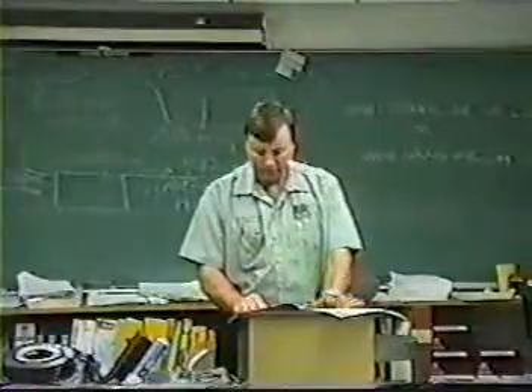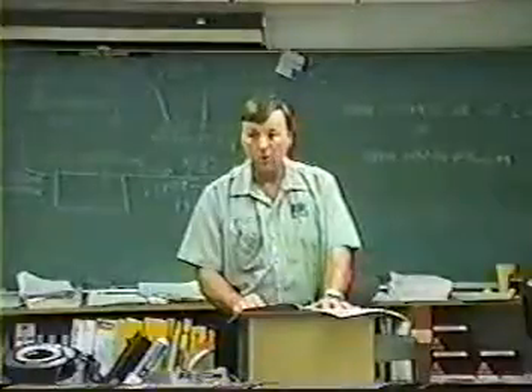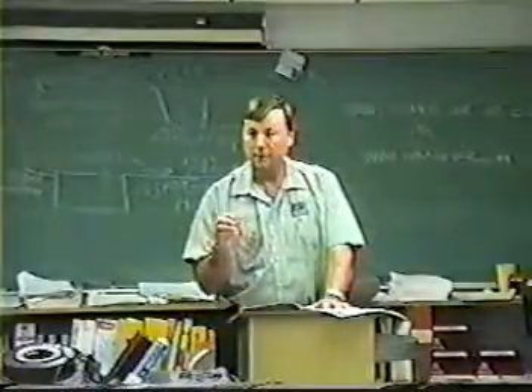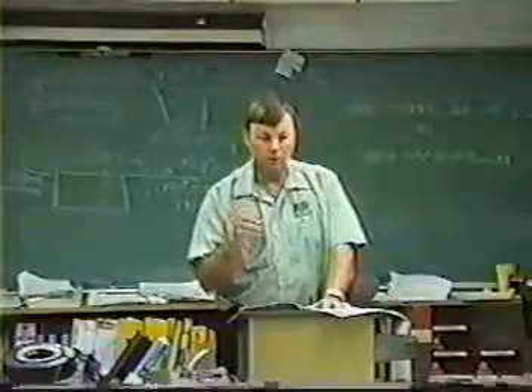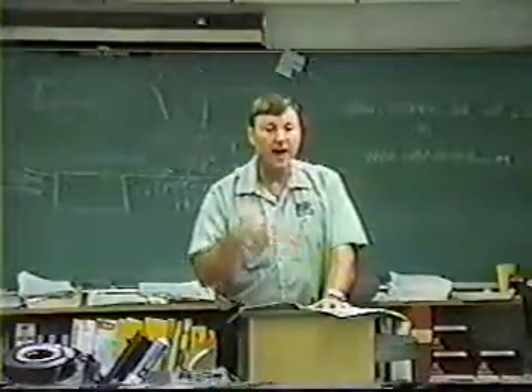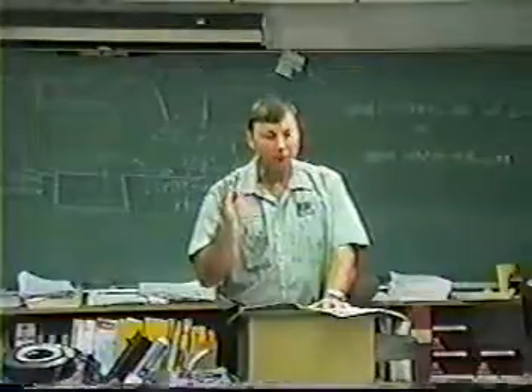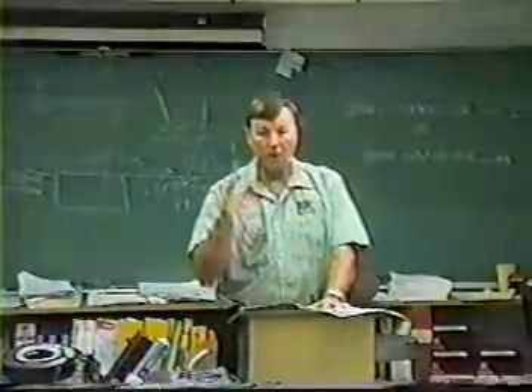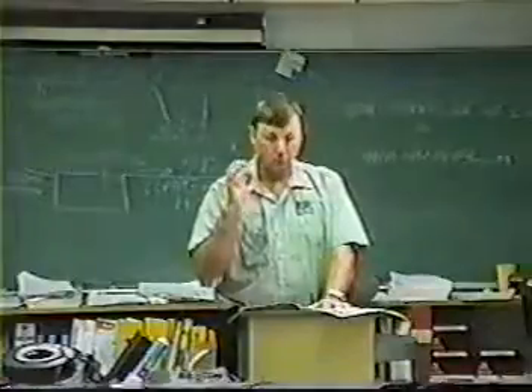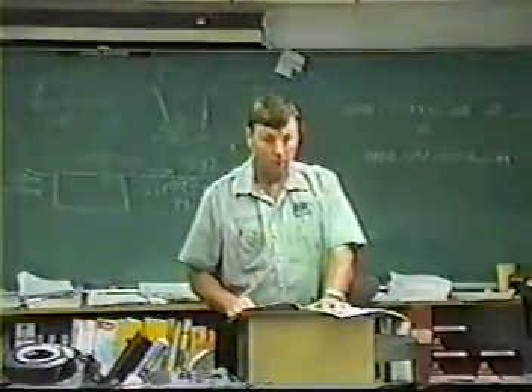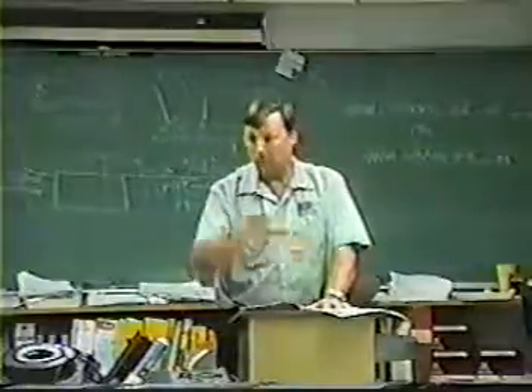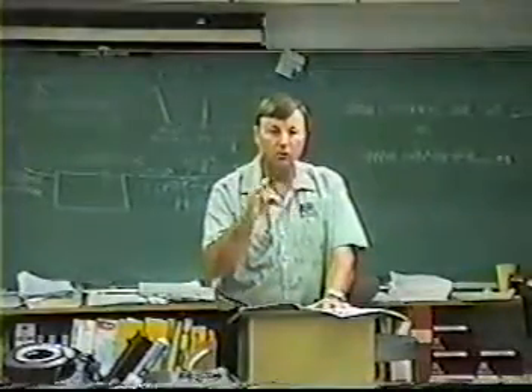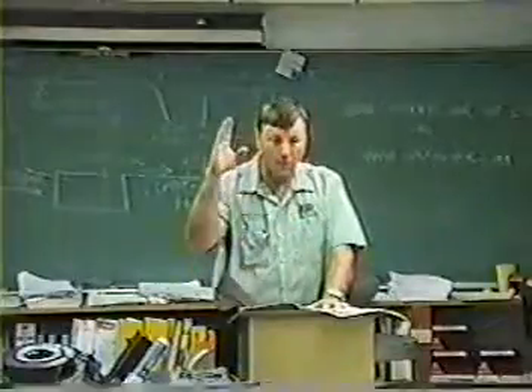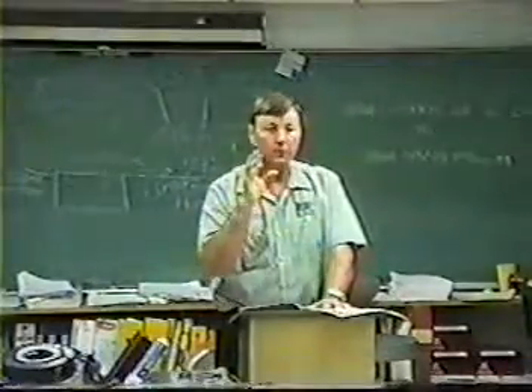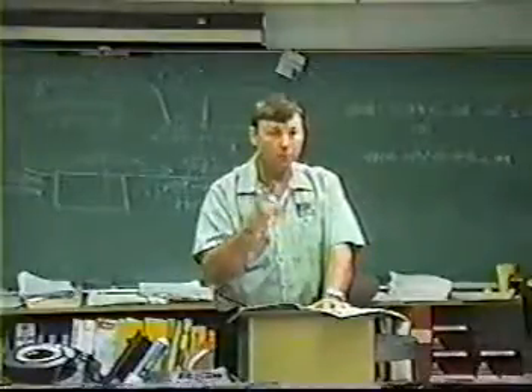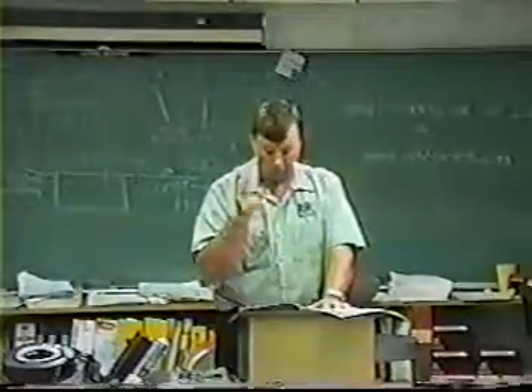That's a tough one. But when you're checking that superheat, you're putting that thermometer on the suction line, and you're getting a high superheat. When I say high, above 20, 25, 30, 40, 50, then you got a good chance you got a Freon leak. And the ones up in this class and before, you know that. And if you're in the field, you've seen it done before too. But high superheat usually is an example of a leak. If you see traces of oil, it's an example of a leak. Now, those both are going to be test questions. They will be test questions.